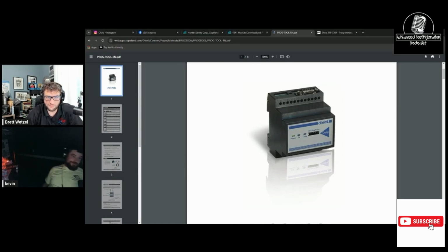Sweet. So did you figure out your VFD cycling yet? VFD cycling. Your VFD. Oh, dude, we still can't get the water loop to be right. So I don't know if the sensor's bad at this point. So we're gonna call tomorrow and call this BTU meter company, because something doesn't add up, because there's flow sensors on the racks, digital flow sensors, and they're all good. What do you mean they're good? How do you know that they're actually giving you the right flow?